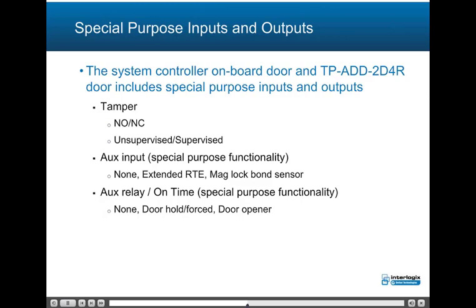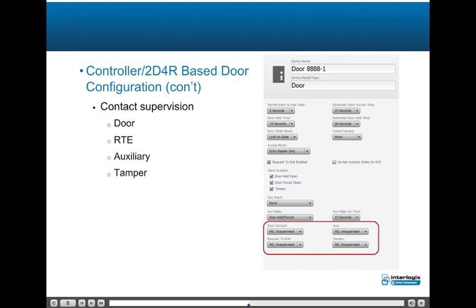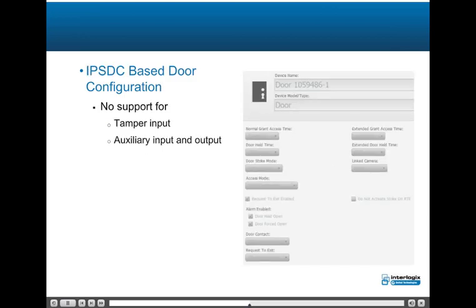The Aux relay on time determines how long the relay remains activated once triggered. The Controller/2D4R based door configuration also covers contact supervision for door position switch, request to exit, auxiliary input, and reader tamper input. Please note that there is no support on the IPSDC-based door configuration for tamper input, auxiliary input, or output.